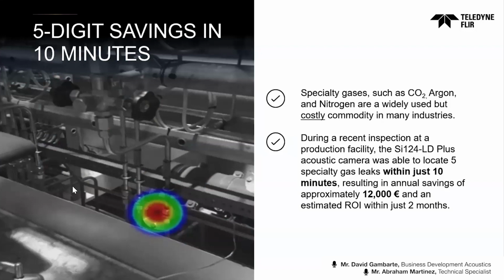During a recent inspection, as you can see here, also using the SI-124LD Plus, even though we already have the SI2 in the market now, so we will soon have examples of the SI2, within just 10 minutes we found 5 leaks that resulted in annual savings of approximately 12,000 euros, which is around $13,000. So the estimated return on investment in this case is just 2 months.